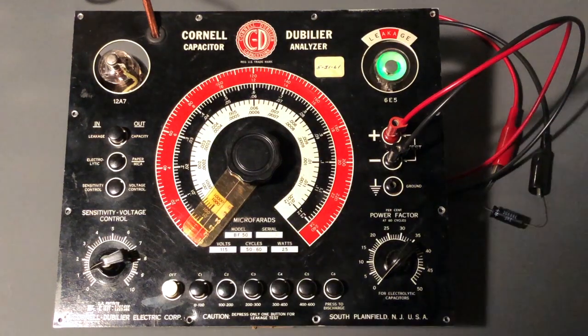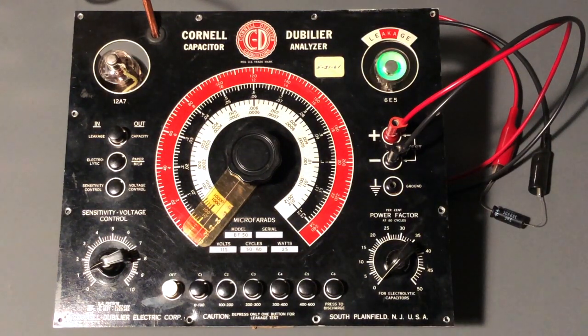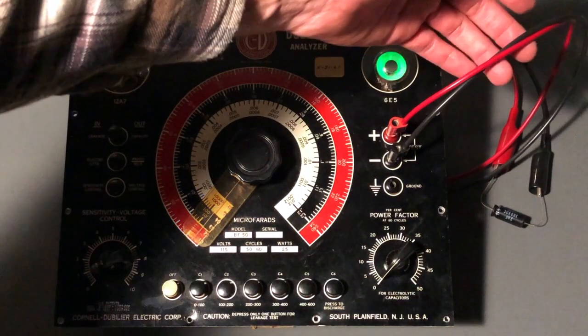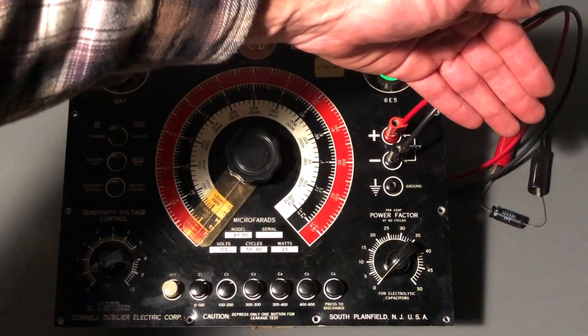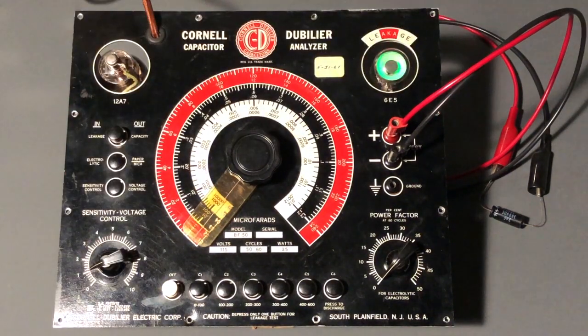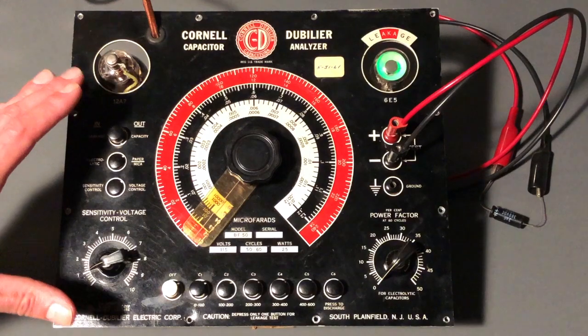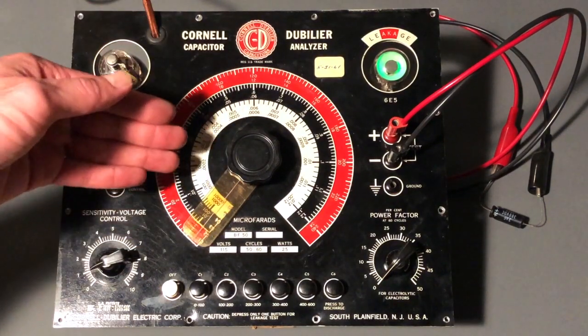Okay, I have the capacitor analyzer set up for the capacity test, and we'll see if our replaced capacitor in that grid circuit solved the problem. Now over here on the test leads, I have a 3 microfarad capacitor attached. It's a known good capacitor, so if the tester is functioning correctly, this dial should indicate at 3 microfarads.